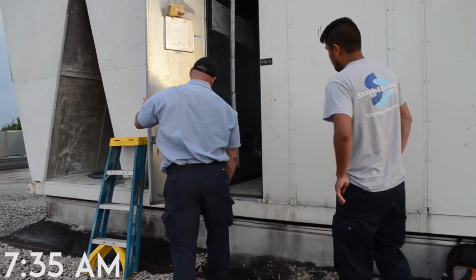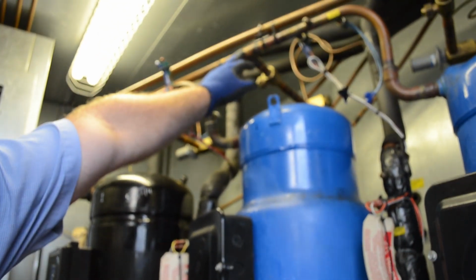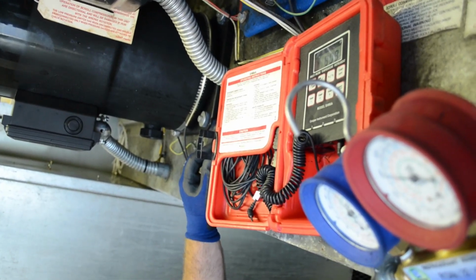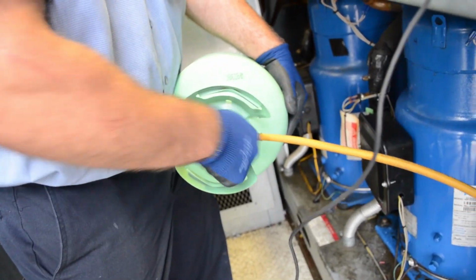So what I'm going to be doing today, there's a rooftop unit that has a refrigerant leak out of one of the refrigerant circuits. There's a total of 8 circuits, so one of them right now is low on charge, and I'm going to add some refrigerant to that circuit to get it back up and running.